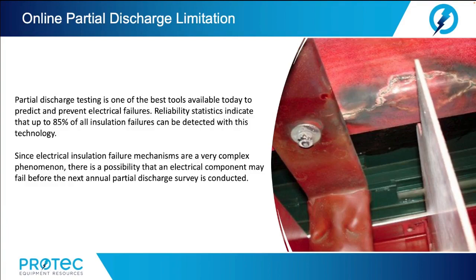Some possibilities that can occur would include human error or accidents, lightning, transients, or switching surges, mechanical failure in the equipment, and insulation damage due to rodents or other pests. Also, the defect can be at an advanced stage. The defect may already be conducting through a carbon path, which acts electrically as a resistor, and no abnormal signals will occur. The partial discharge source may be inactive at the time of the test. It can contain defects that may vary with humidity, temperature, or other conditions.